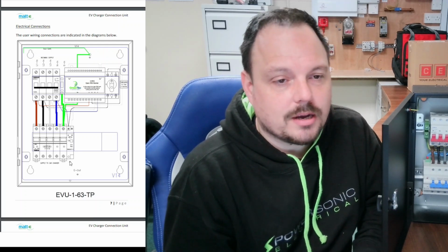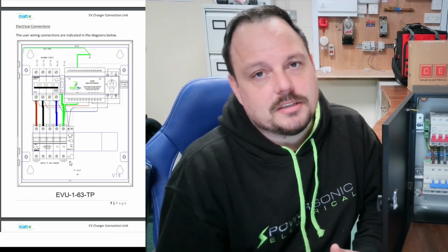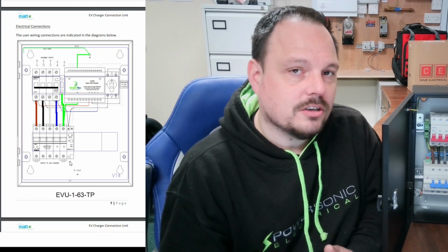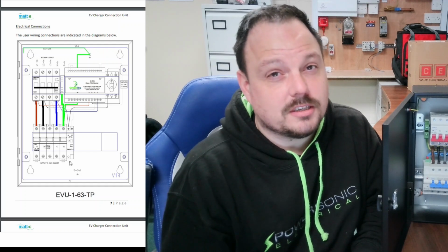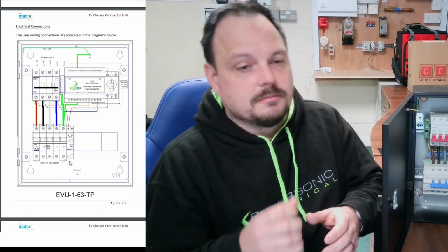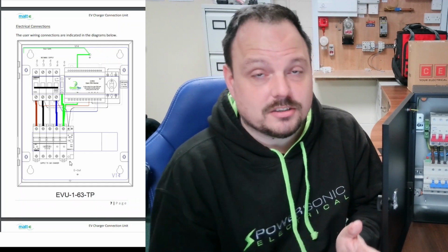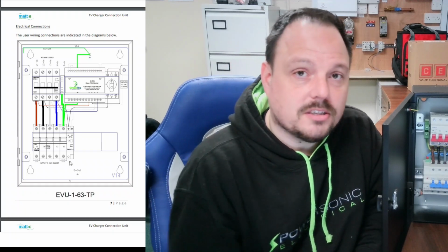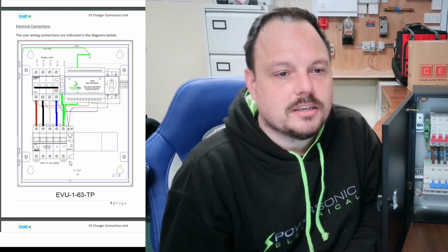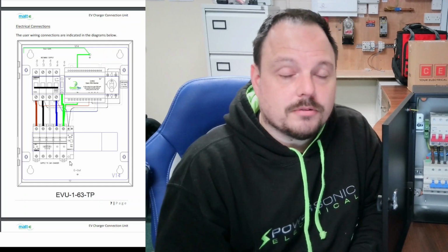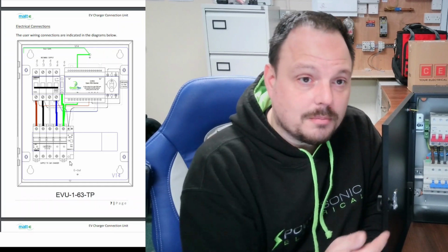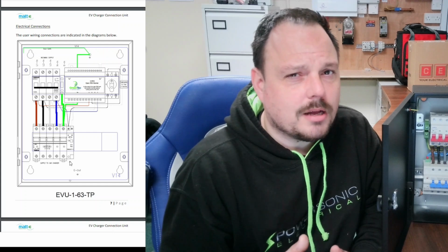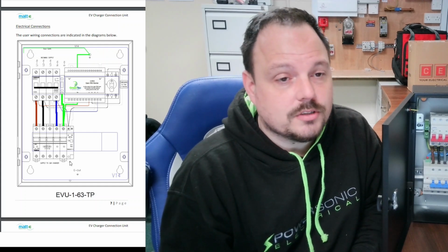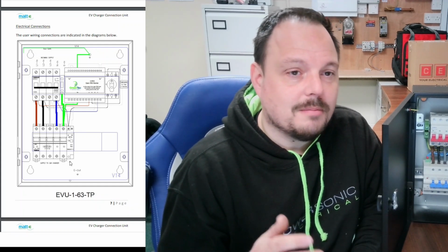If you are using steel wire armor cable, take it from the Matt-E, but isolate it at the load end away from the charge point. Because obviously if you are bypassing essentially the Matt-E, if you take the steel wire armor and gland it into the charge point itself and connect it into the CPC at the load end, if this operates and opens the CPC inside the Matt-E, you're still going to have that connection. So I hope that makes sense. And there are different ways of doing this. People do it in all sorts of different methods.